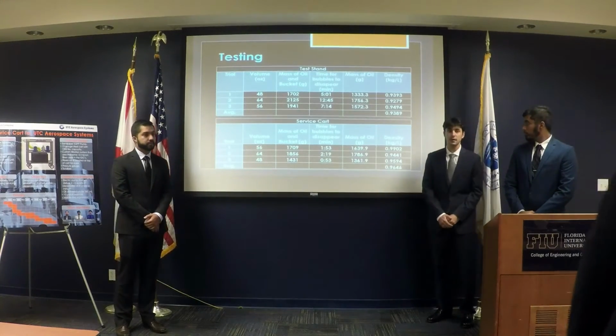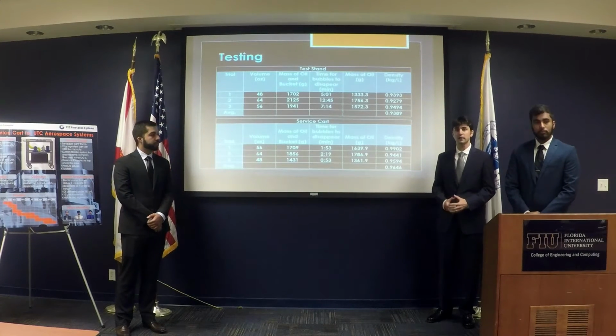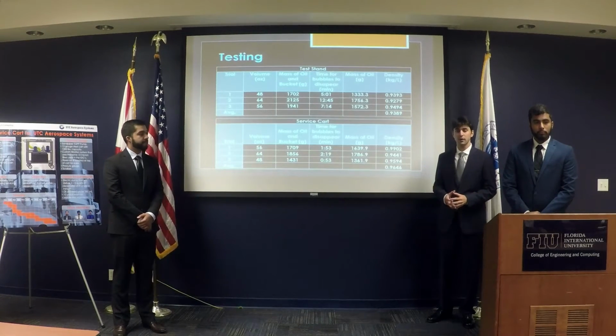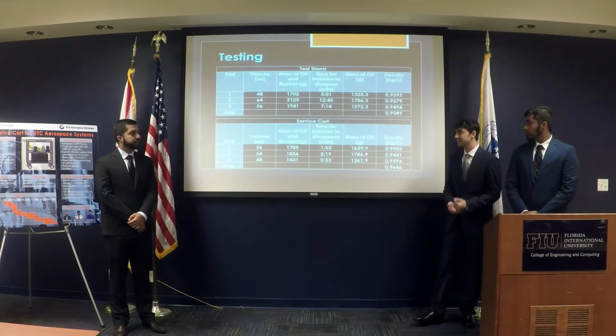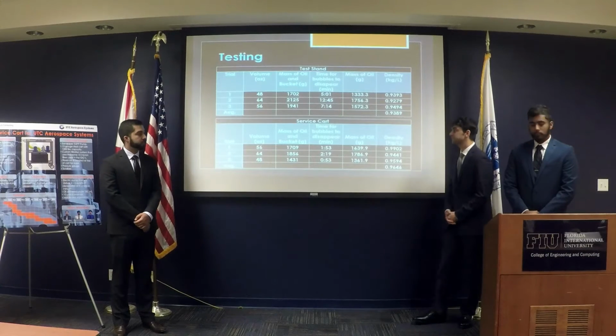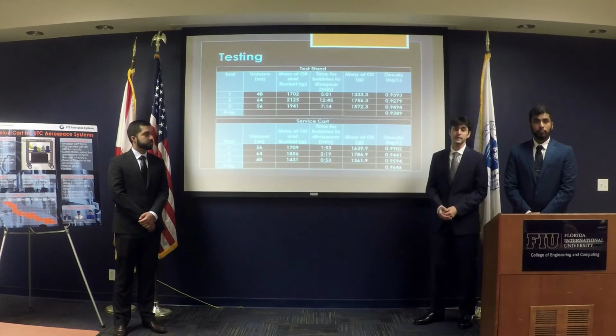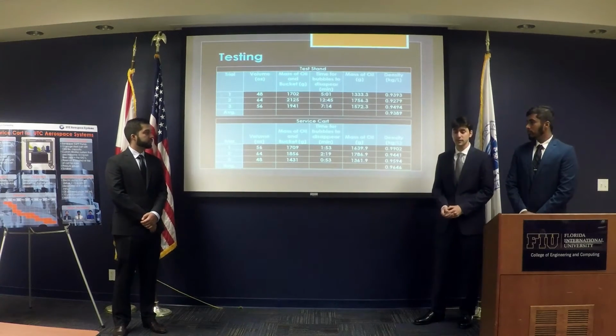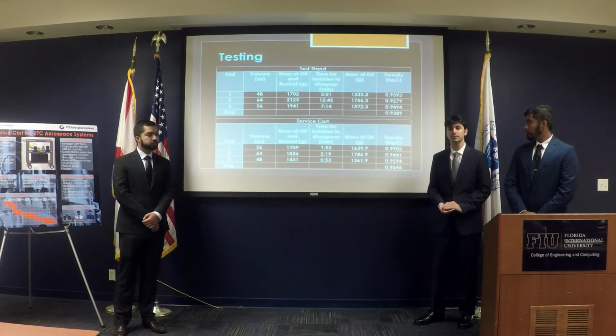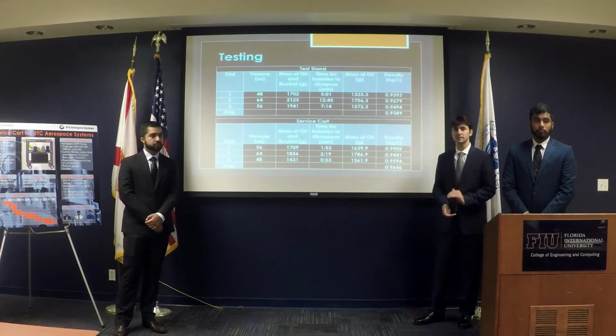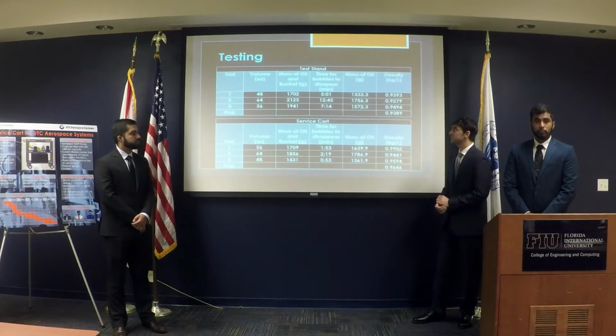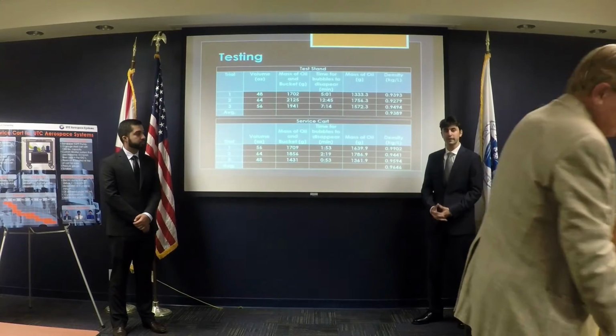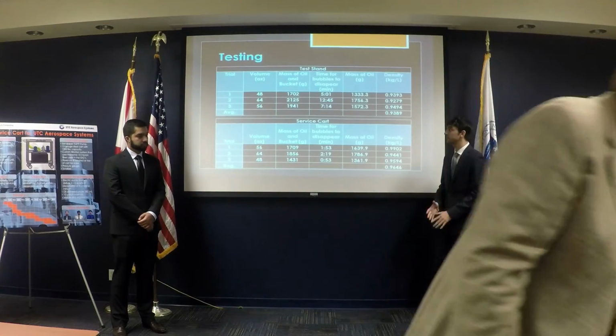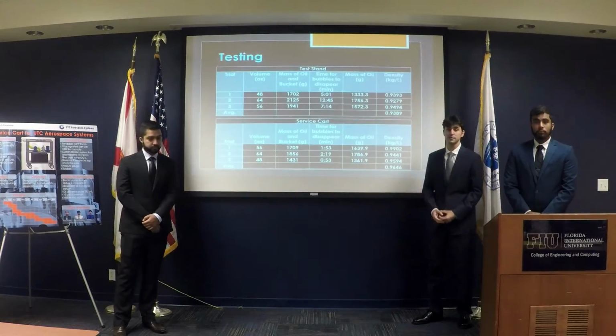Now theoretically, a sample that has more air content, taking up that oil's volume, would give a lower density. So a higher density would mean there is less air in that sample. Also, what we did was we started a stopwatch and timed how long it took for the air bubbles to rise up to the surface and dissipate out of the oil. As you can see from the test stand, we get a rough view of how the air bubbles behave in the oil. It took anywhere from 5 to 13 minutes for the oil bubbles to come up to the surface.